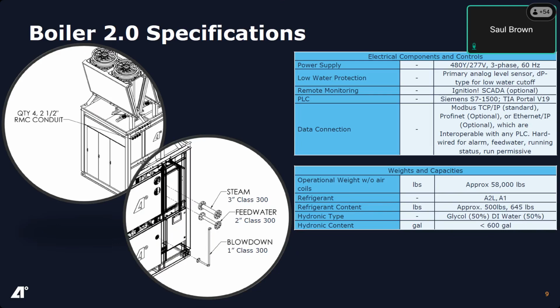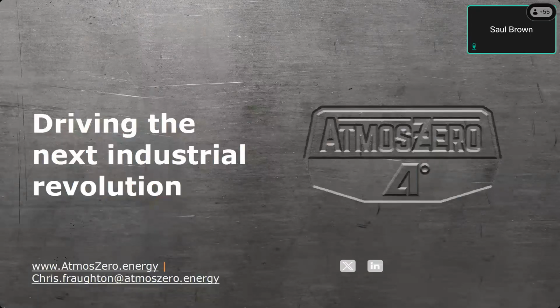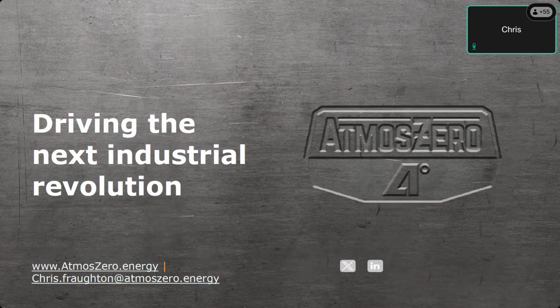Question on capacity and on the price compared to regular heat pump chillers. Capacity, so we're a 1 megawatt thermal system as a nameplate. Call that a nominal number. Again, it depends on what the steam output pressure is. So if you're a lower pressure system, that'll be a little bit smaller, anywhere between like 850, 900 kilowatts, which is about 3,000 to 3,400 pounds an hour. But then from there, you also have turn down. So to give you a rough range, call it mid 2,000 pounds an hour to 3,400 pounds an hour.